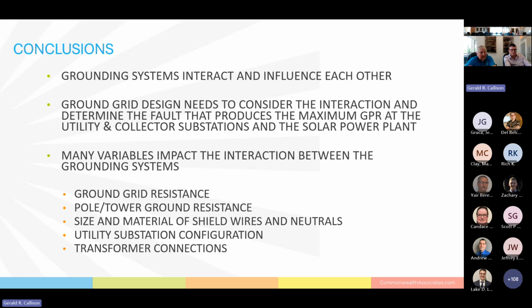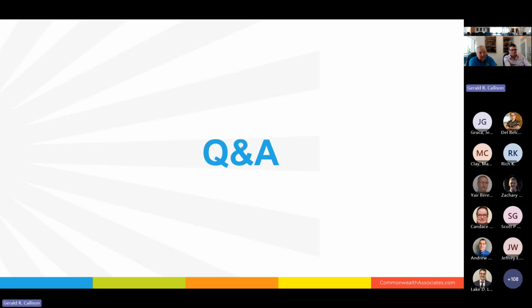Those facilities can vary tremendously. If you've got a solar plant and you've got thousands and thousands of poles supporting those solar panels, each one of those is basically a ground rod sticking in the ground. And the resistance of that solar plant, the larger it gets, the lower the resistance is going to be. And that's going to have an impact too, because the current is going to go wherever it can, through the lowest resistance, to get back to its source. So with that, we can move on to the question and answers.